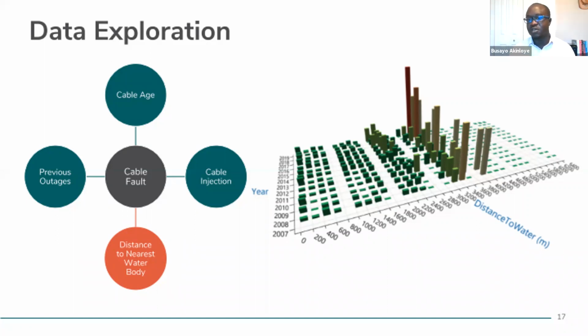This was quite interesting, but we also considered that correlation doesn't imply causation—there could be a middle factor such as age. It could be that older cables happen to be farther from water, depending on when the city started building out. So we normalized for age, and we still found the same trend: farther from water meant a higher chance or higher number of failures. That was quite interesting to us.